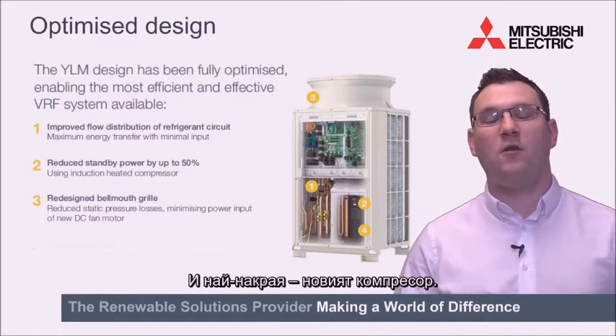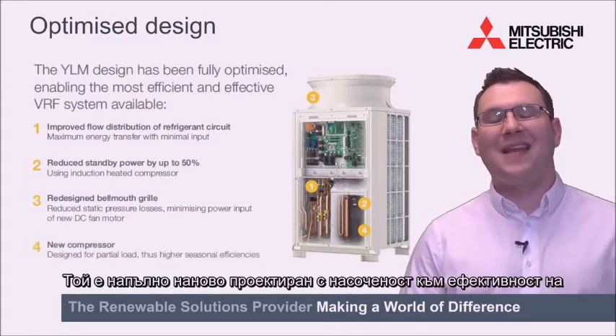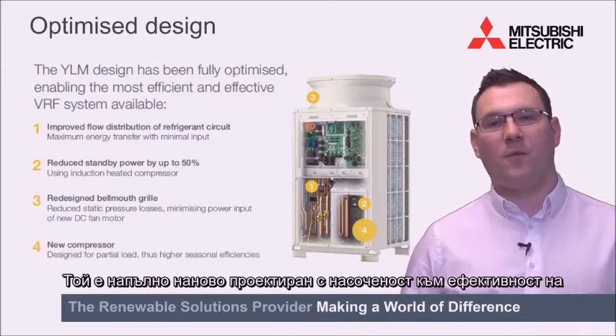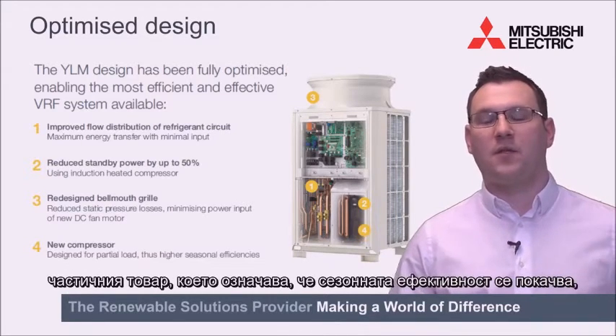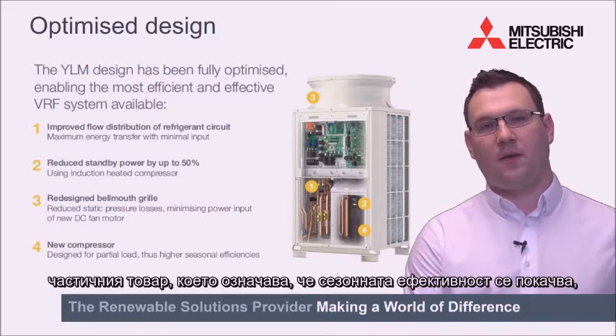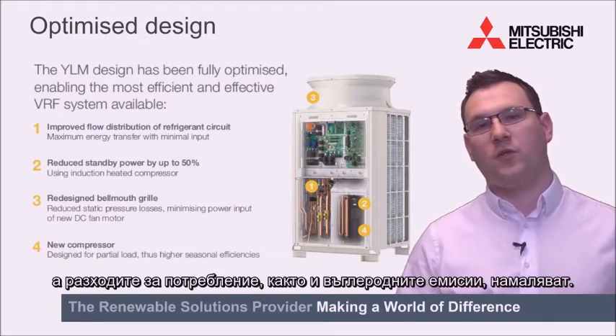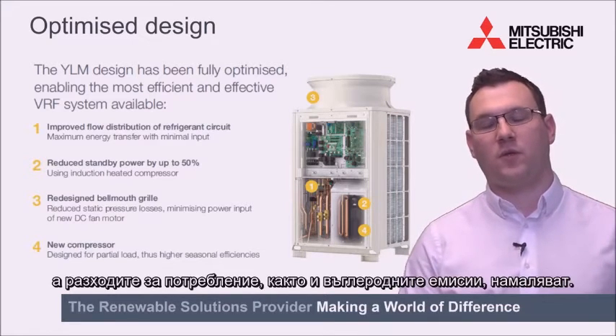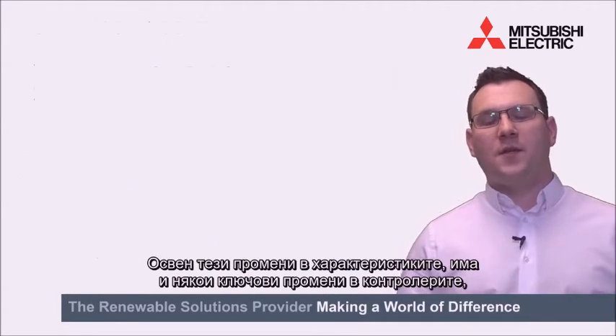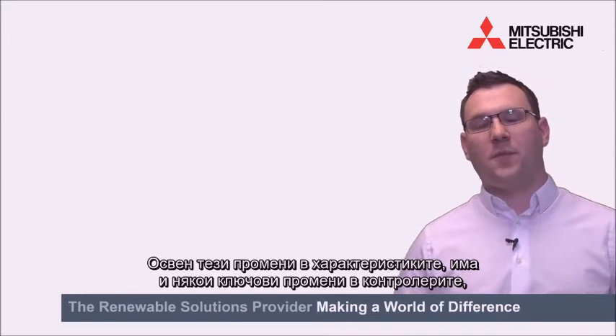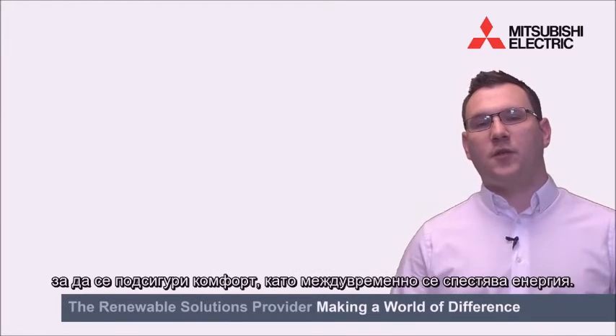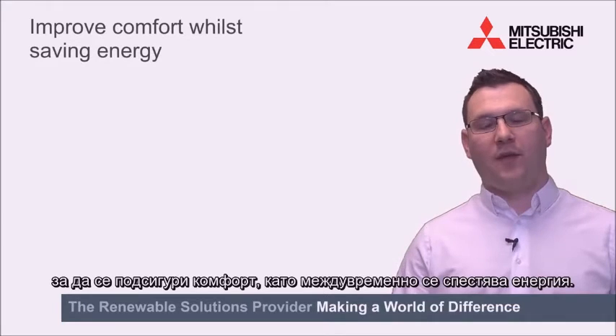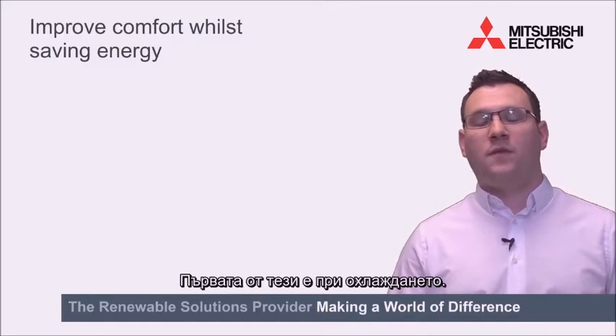And finally, the new compressor. This has been completely redesigned, away from a peak load efficiency towards a partial load efficiency, meaning that the seasonal efficiencies are increased, running costs are reduced and CO2 emissions also reduced. So as well as those key physical changes, there's also been some key controls changes to improve the comfort whilst also saving energy. The first one of these is around the cooling side.